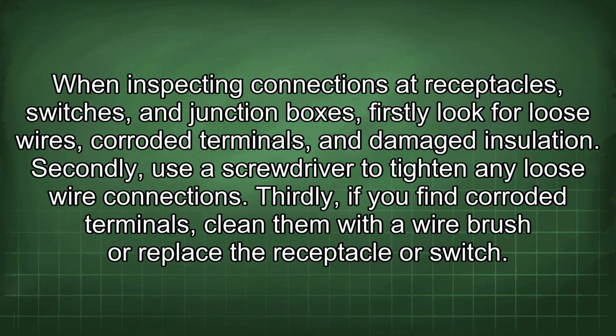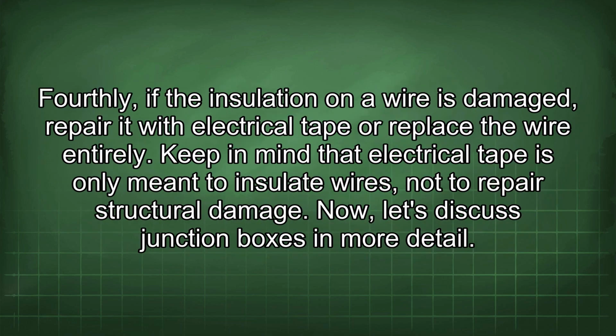When inspecting connections at receptacles, switches, and junction boxes, firstly look for loose wires, corroded terminals, and damaged insulation. Secondly, use a screwdriver to tighten any loose wire connections. Thirdly, if you find corroded terminals, clean them with a wire brush or replace the receptacle or switch. Fourthly, if the insulation on a wire is damaged, repair it with electrical tape or replace the wire entirely. Keep in mind that electrical tape is only meant to insulate wires, not to repair structural damage.